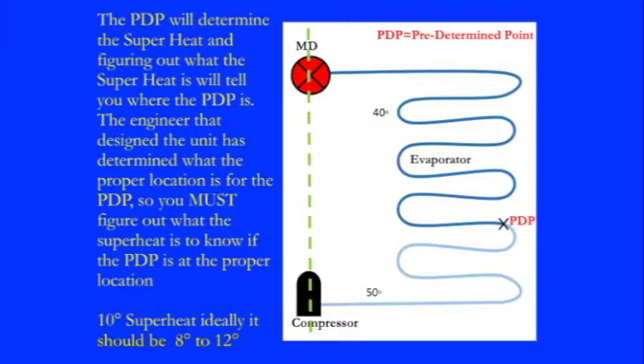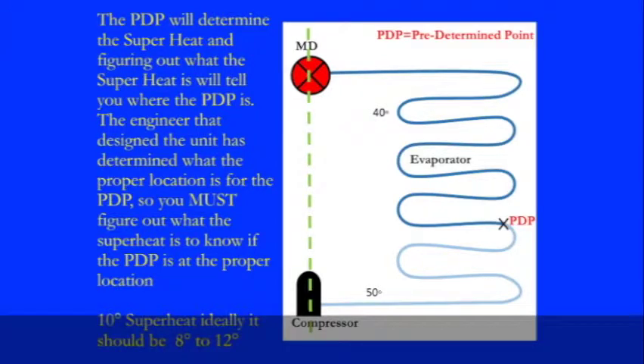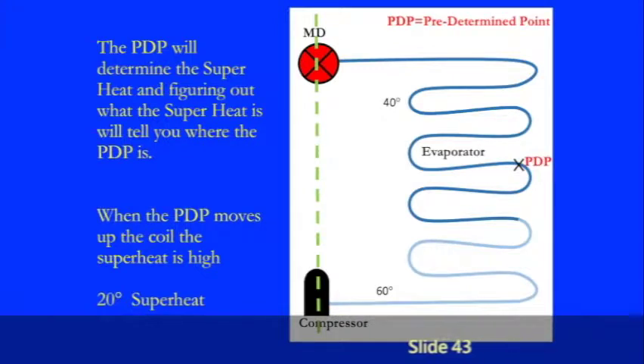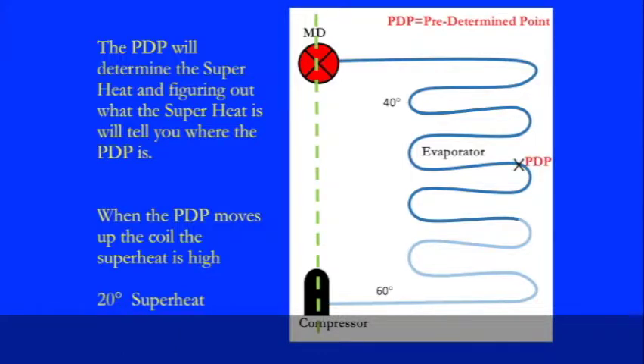Now, if we look at slide 43, we see the pre-determined point has moved up the coil. It's superheating after the pre-determined point, but because of that, it's superheating in a much larger area. Because of that, the outlet temperature is now 60 degrees.